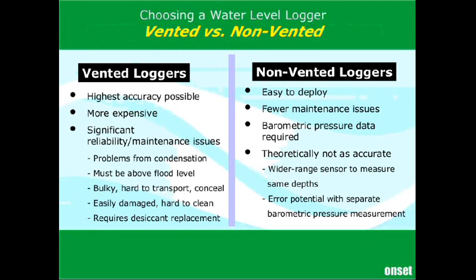But extra maintenance trips can be expensive depending on the distance you need to travel, and it requires changing of the desiccant to keep it clean. The non-vented logger gives you an accurate measurement, not quite as good as the vented logger, but nevertheless it's easy to deploy, easy to maintain, and usually gives you very good data. As far as the barometric pressure reading goes, it does help to have a second pressure logger in the area, although one can use hourly local weather station data if required, and if the software that comes with the system accepts external barometric data and has the ability to interpolate the data so that sample rates and start times do not need to be controlled.